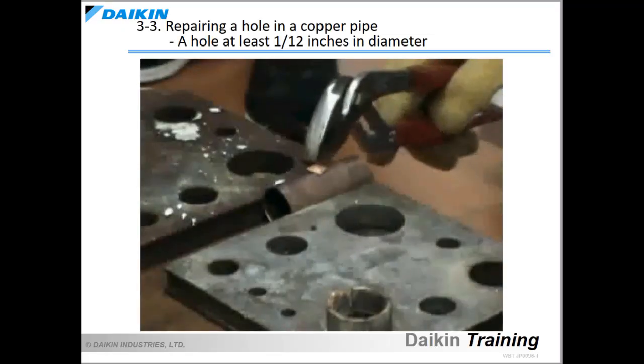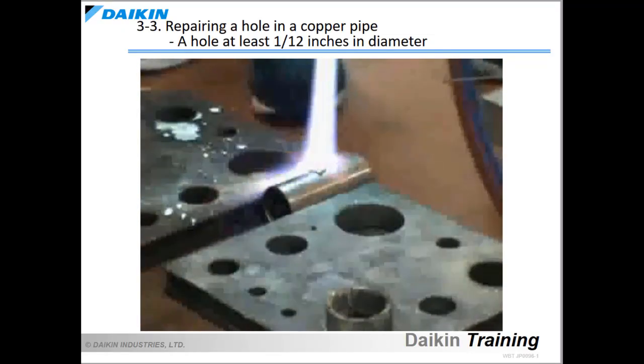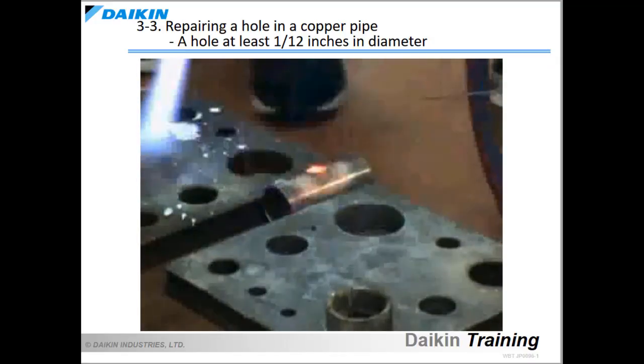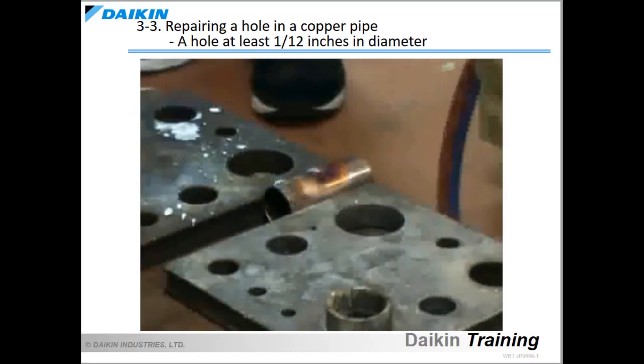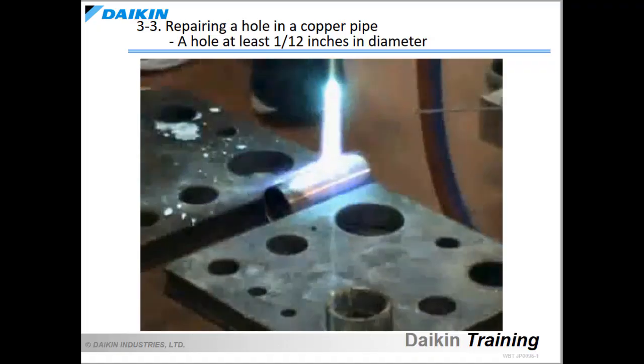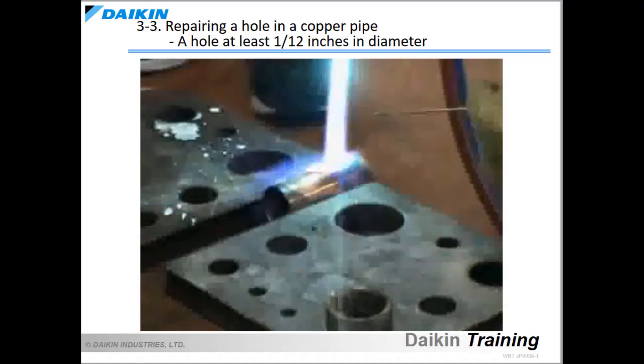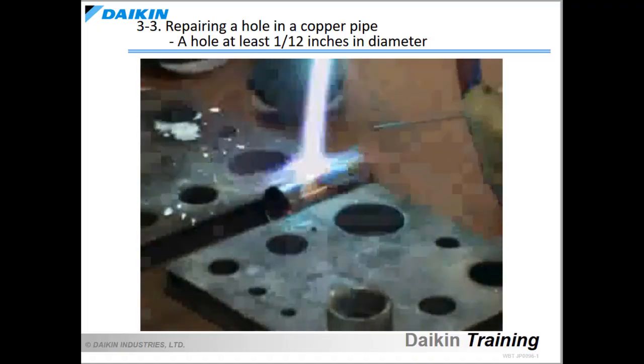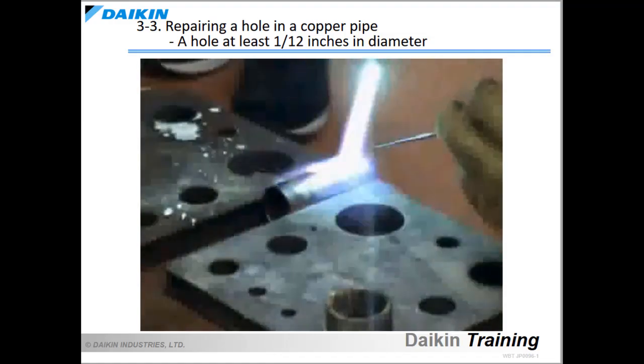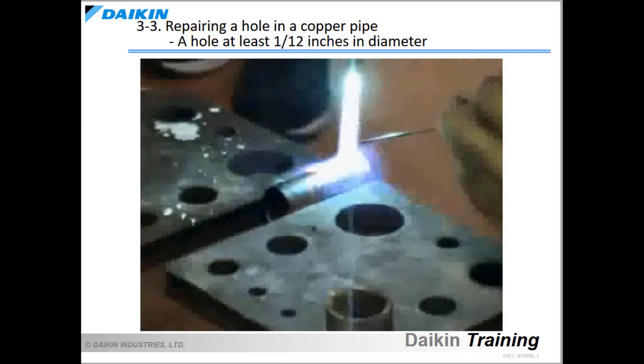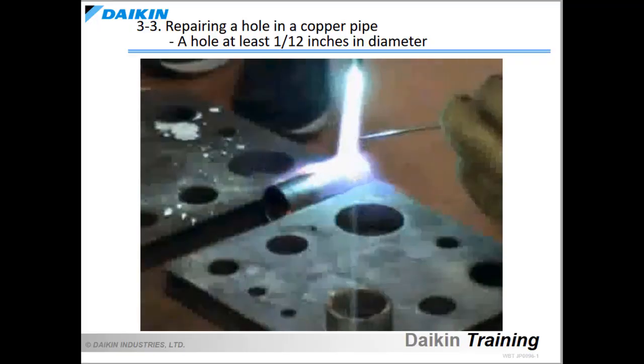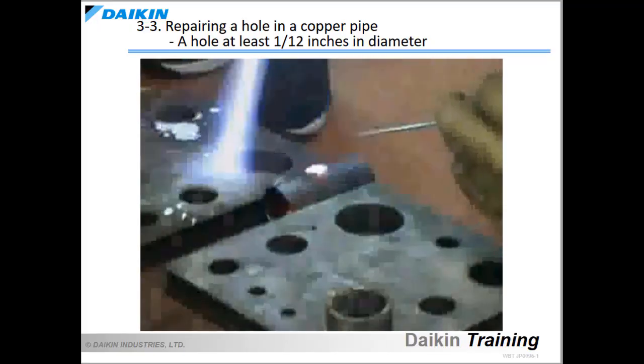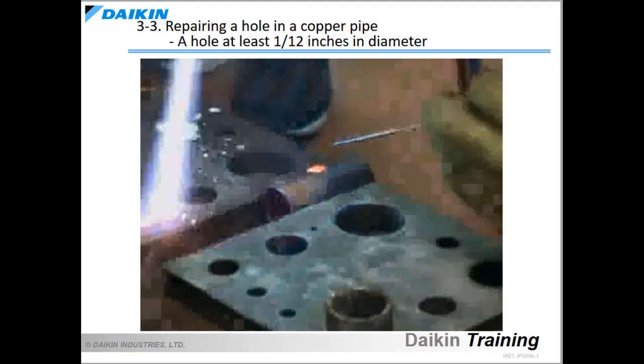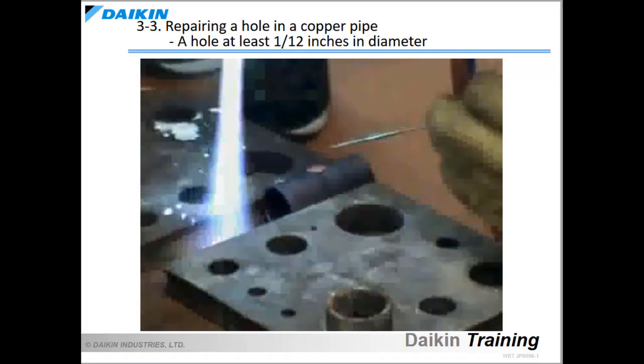Let's now learn about the repairing of a hole in the copper pipe in the video. First, put the copper sheet on the hole. Light the torch and adjust the flame intensity. Use the reducing flame. Apply the flame at a distance from the copper sheet to heat it. After the copper pipe is heated to the appropriate temperature, distribute the brazing filler metal into the gap between the copper sheet and copper pipe to cover the hole.